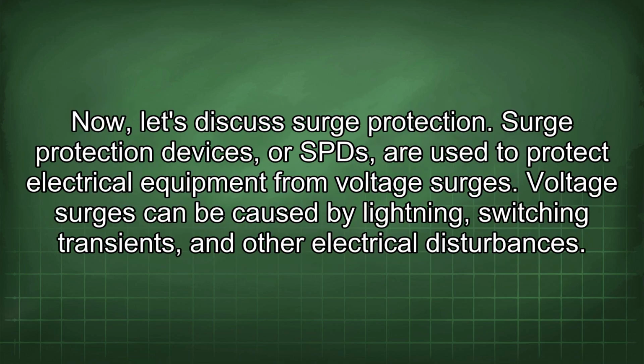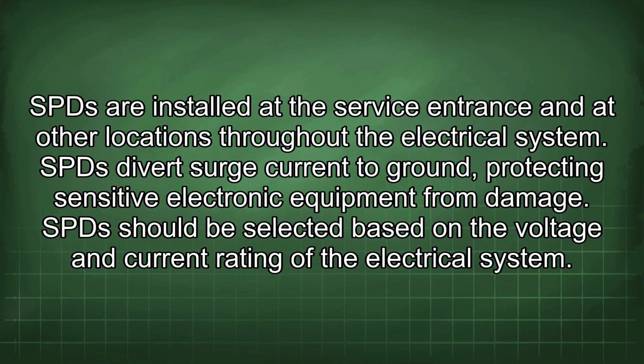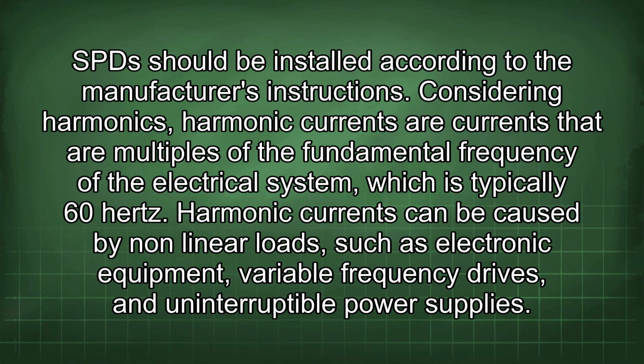Now let's discuss surge protection. Surge protection devices, or SPDs, are used to protect electrical equipment from voltage surges. Voltage surges can be caused by lightning, switching transients, and other electrical disturbances. SPDs are installed at the service entrance and at other locations throughout the electrical system. SPDs divert surge current to ground, protecting sensitive electronic equipment from damage. SPDs should be selected based on the voltage and current rating of the electrical system. SPDs should be installed according to the manufacturer's instructions.